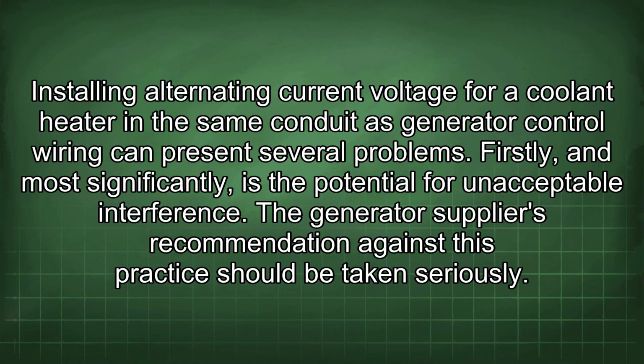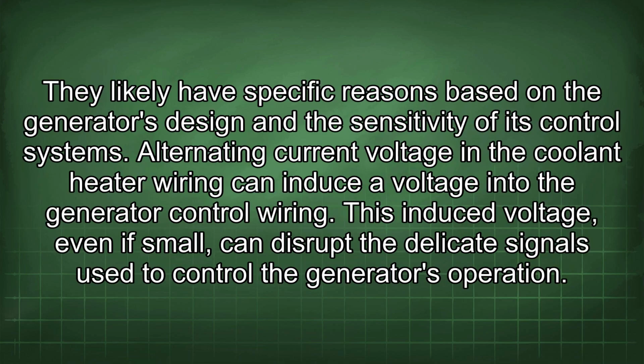Installing alternating current voltage for a coolant heater in the same conduit as generator control wiring can present several problems. Firstly, and most significantly, is the potential for unacceptable interference. The generator supplier's recommendation against this practice should be taken seriously. They likely have specific reasons based on the generator's design and the sensitivity of its control systems.